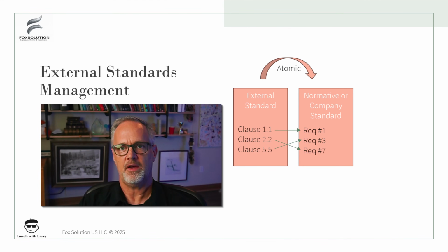For example, if you have a sterilization document and the product line is syringes versus maybe pacemakers, you're going to deploy ethylene oxide sterilization differently for those. In some ways, it's the same. The external standard is going to give you that generic view, but how you're going to deploy it for this device type is likely to be different inside your company. And it's also intellectual property as to how it is that you're going to do that.